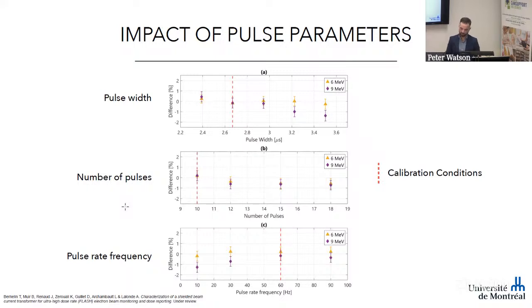We were very stable, again, within 1% with the number of pulses, and stable also with pulse rate frequency, which also can affect the beam energy. So we think all these discrepancies come from changes in energy. So one way to account for this in the clinic, even though the changes are not very large, would be to just check the energy prior to irradiation, which is something that the beam current transformer cannot do. It just reports the current. It doesn't report the energy. So it needs to be matched with another detector that could do some energy check prior to irradiation.